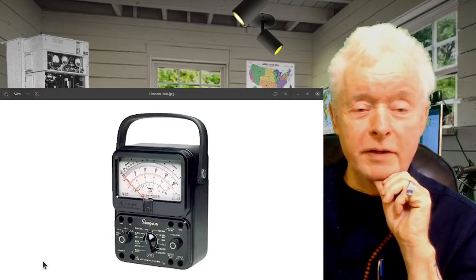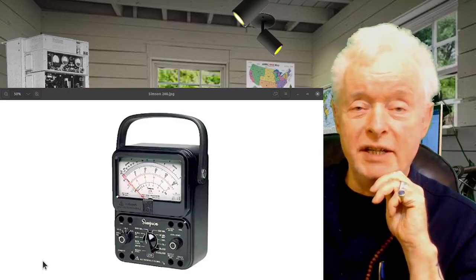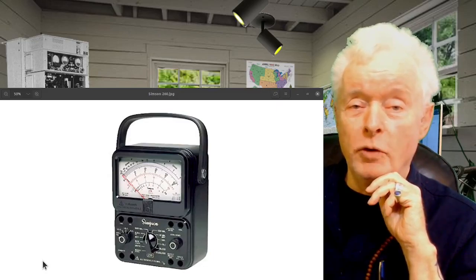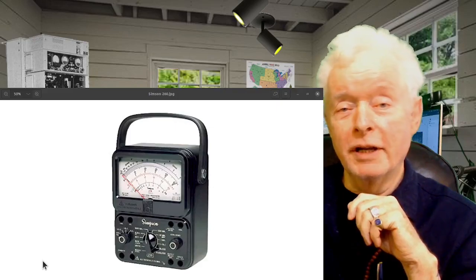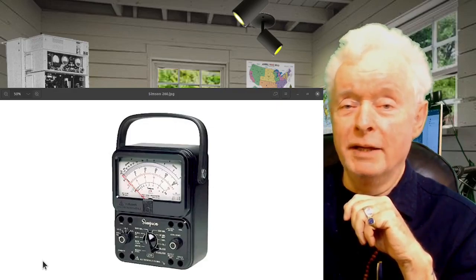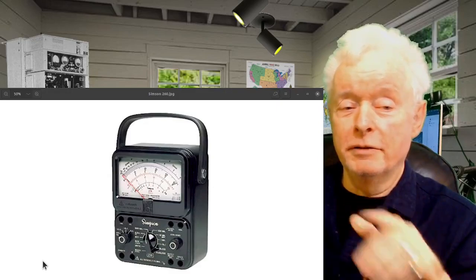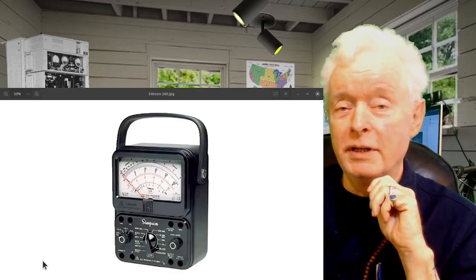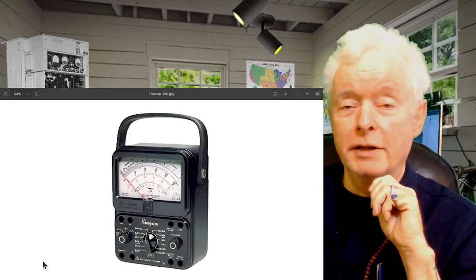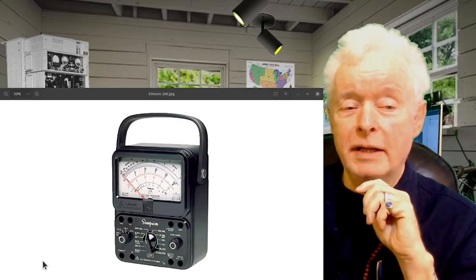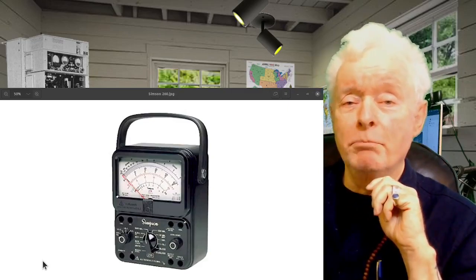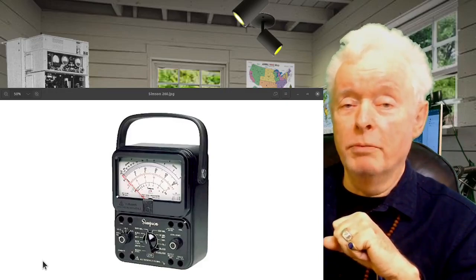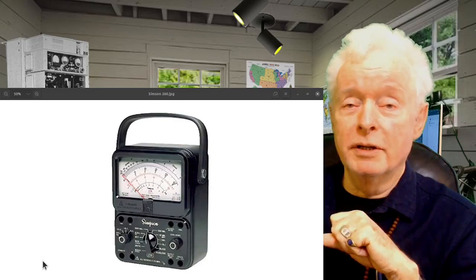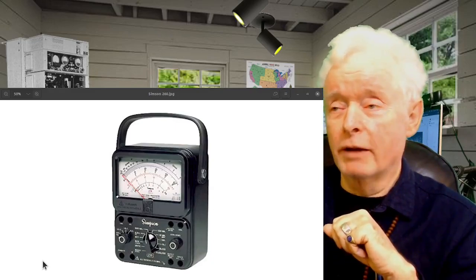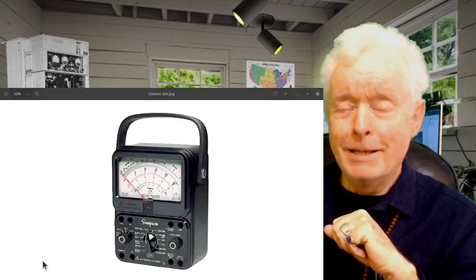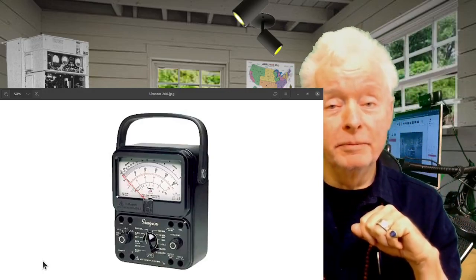Okay, here we have a Simpson 260. This is a classic voltmeter from my days in the Navy, and certainly is rugged to beat the band. It contains a lot of function in it. You'll notice that the switch there is grouped into current, voltage, and ohms. And I believe this particular meter has a mirrored scale, so that's one of the more precision meters. Mirror scales typically give you an accuracy of about, good ones, 1% of full scale.